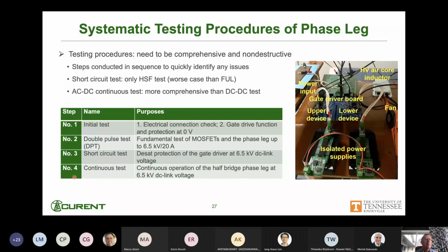These are steps where we were very deliberate, making sure all the connections checked out, that our gate drive functions were working properly, before even connecting it up to the device itself. The second thing we did was quite a bit of double pulse testing to check how the device was working. Then we moved into short circuit tests, and finally continuous tests, since we want to operate it continuously. You don't want to jump ahead in the testing sequence, build something, and just go see if it works.